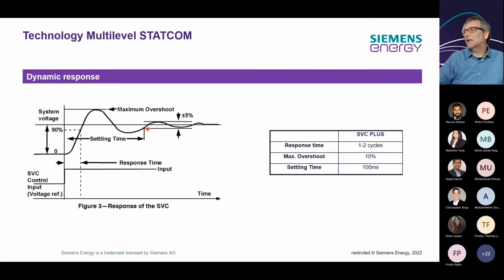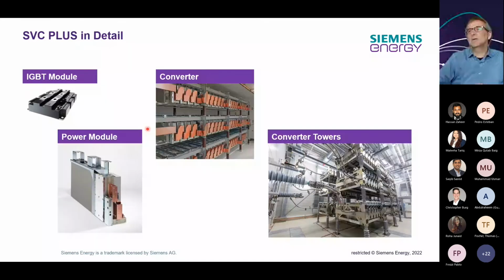If we have a look at how such a converter would look, we have the IGBT modules. We have the power module with the DC capacitors. And if we put all those in series, we can see the 3 phases here. Or we have the full converter connected, 2 converters in parallel, or they're connected in the back. So it means it is 1 row in series. This is how we can build it, the SVC Plus.